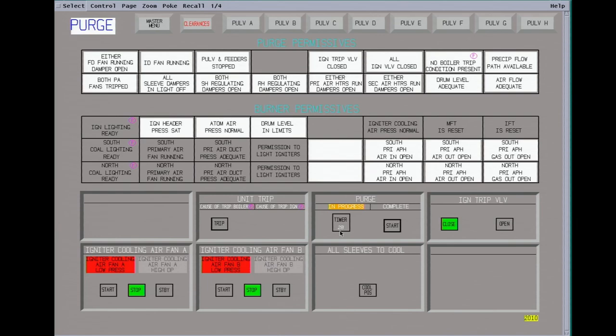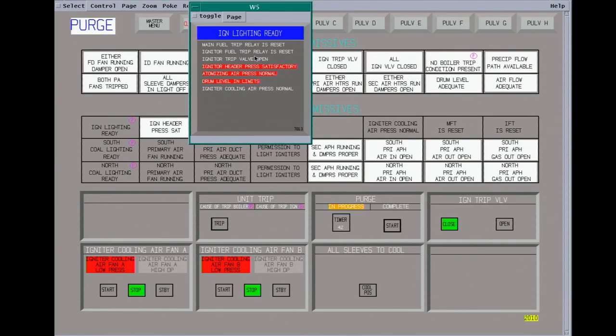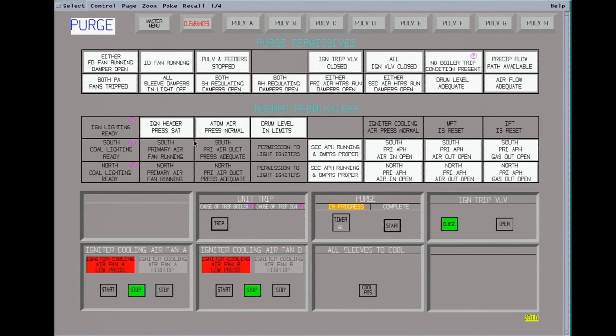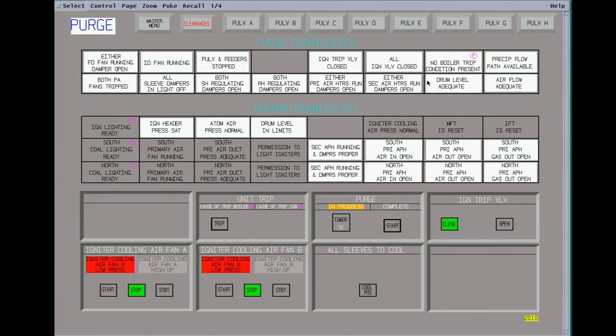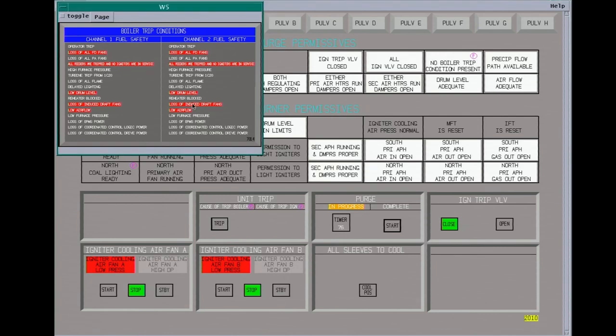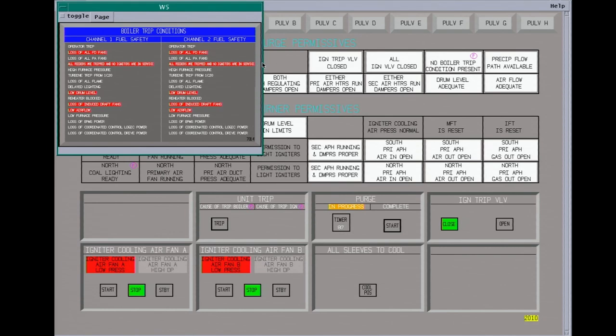Okay, on our purge permissive screen, we have all the permissives and it has started purging. It has to go through a five minute timer. It's kind of nice on these screens. A lot of the newer plants have this where you can go to your permissive screen and see what you do not have made up yet. So we can't start the igniter because the main fuel trip isn't reset and the cooling air is not running for the flame scanners. But the boiler won't start until it's completed its purge. It is part of the boiler trip lockout circuit. This is all the boiler trips. So there's a lot of things that will trip these units.